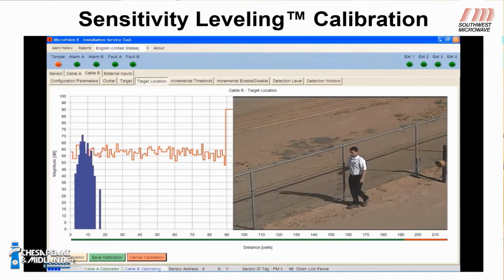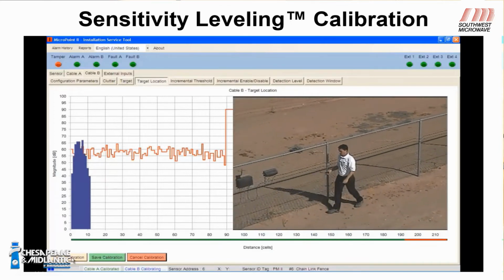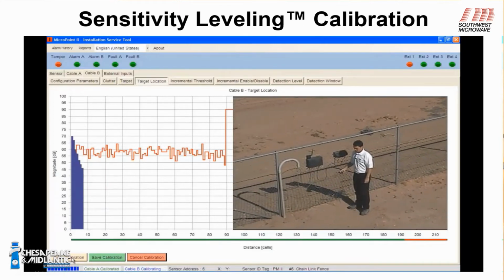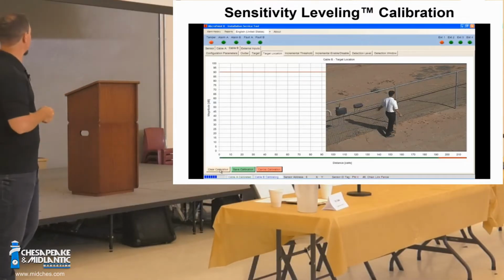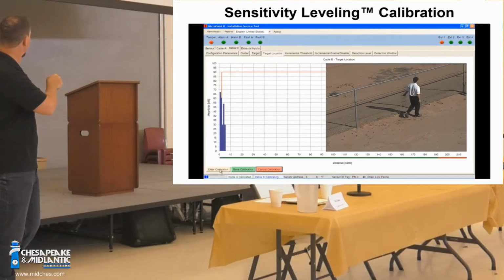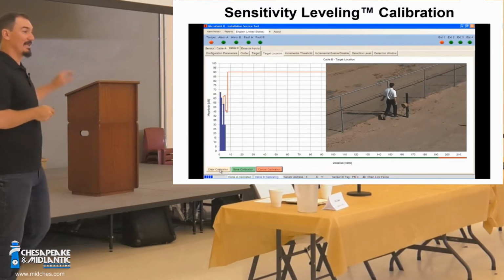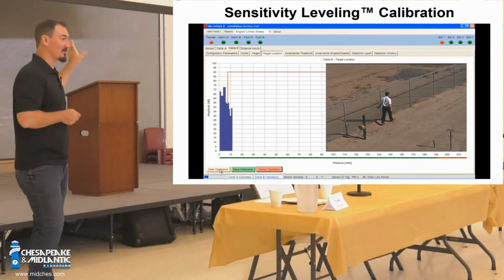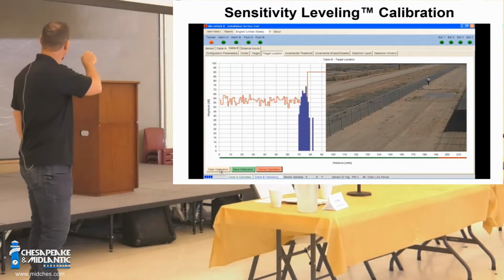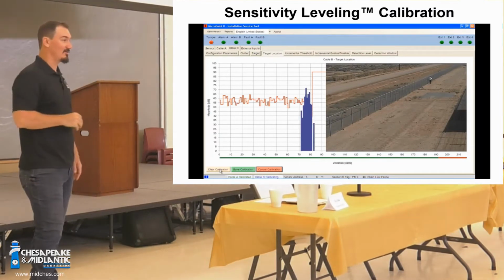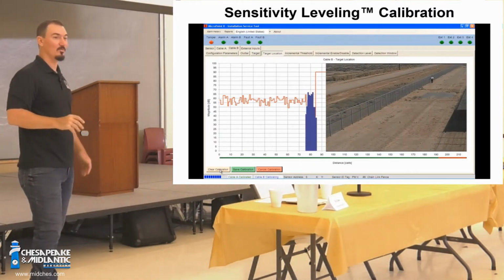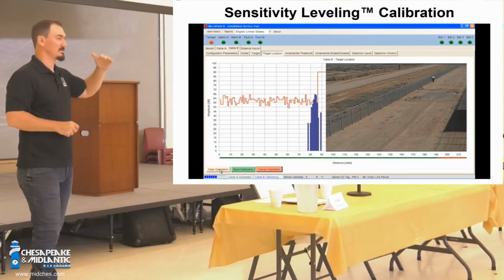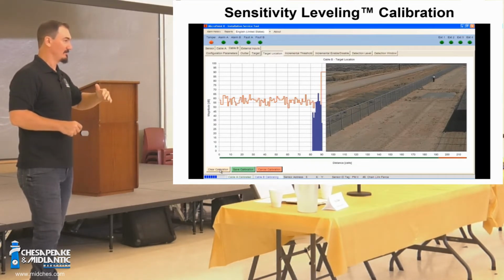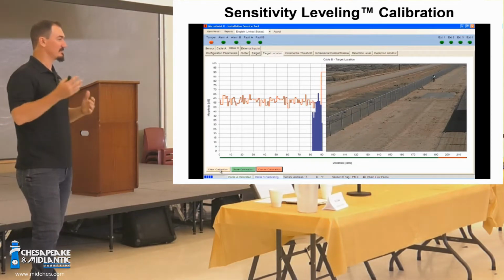This section of cable is attached to this fence panel, and this is what typical vibration looks like on this panel, calibrating it to the system. So you'll notice they're not flat. Some are higher, some are lower. That's a good thing. If your installer comes in and changes this to make it a flat line, they don't know what they're doing. They did it wrong. You want some to be higher. You want some to be lower. That is a specific response to that section of cable.